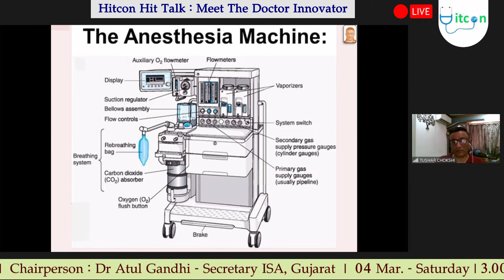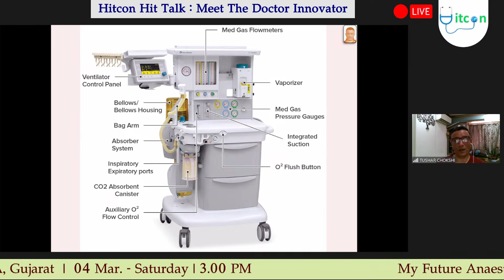And these are the parts in modern machines: ventilatory settings and ventilatory parameters and monitors, vaporizers, all types of vaporizers mounted in one bag, absorber system, CO2 absorber canister, all types of alarms, medical gas pressure, how the oxygen is supplied and where it goes. So they have an O2 flush button, and there are all the facilities you can have. And to learn this machine in the anesthesia curriculum is sometimes very difficult, in the junior part also. But now, day by day, it is becoming very easy.